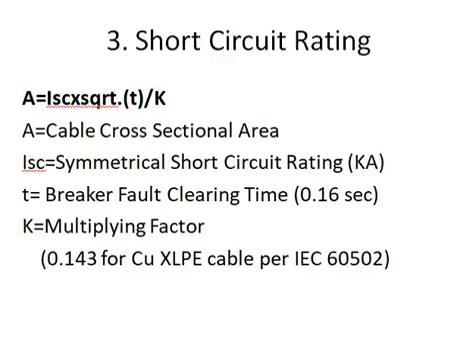If this criteria is also fulfilled by the preliminary selected cable size and number of runs, then your cable size selection is finalized. Otherwise you need to modify the cable sizing accordingly. To select the proper cable size for breaker operated motor feeders, you need to satisfy all three criteria. For MCCB operated feeders, only the first two criteria need to be met. I hope you liked this video — please hit the like button and subscribe to my channel. Thank you.